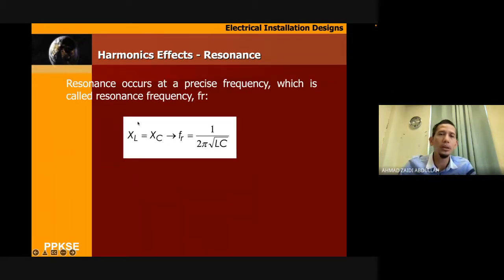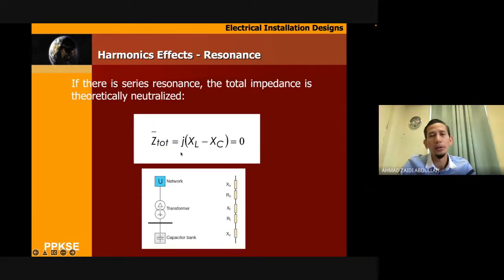Okay. So resonance occurs at a precise frequency which is called resonance frequency, FR. Normally when we deal with harmonic, it disturbs the frequency, because the frequency should be steady. So frequency we normally define under 1/(2 pi f), 2 pi f. So here we deal with L and C. So XL equals XC, so we can calculate using 2 pi root LC, and then we can neutralize it. If in series, jXL minus jXC, it should become 0, right? So that's why we connect it in series connection.